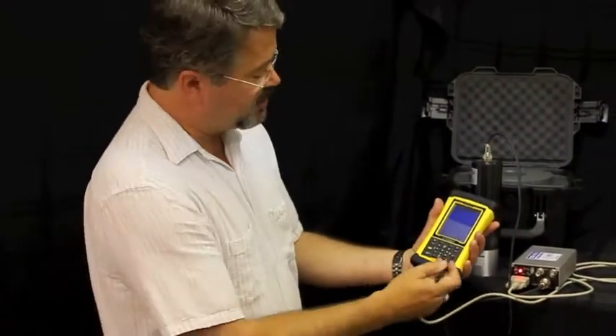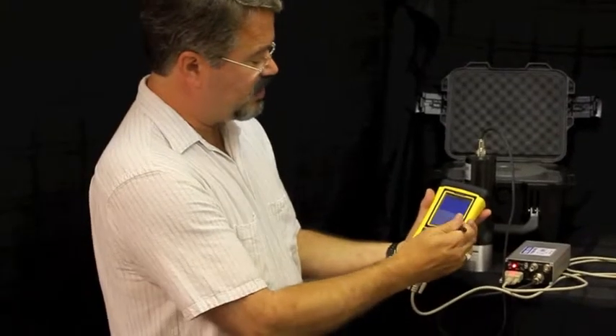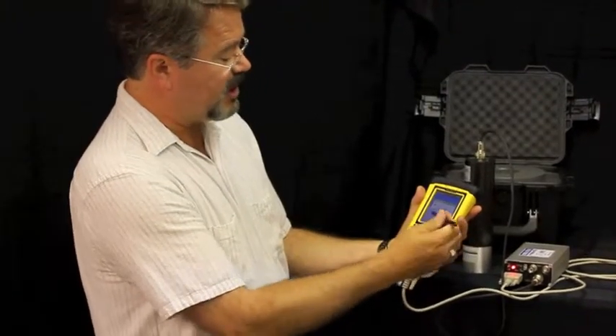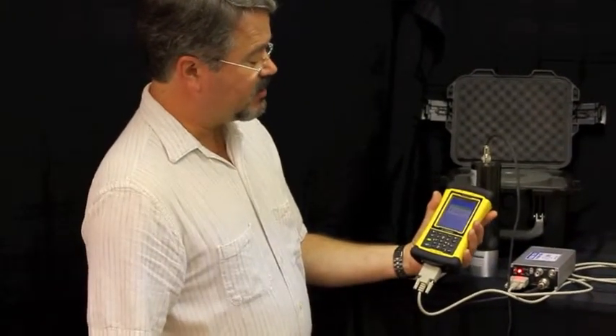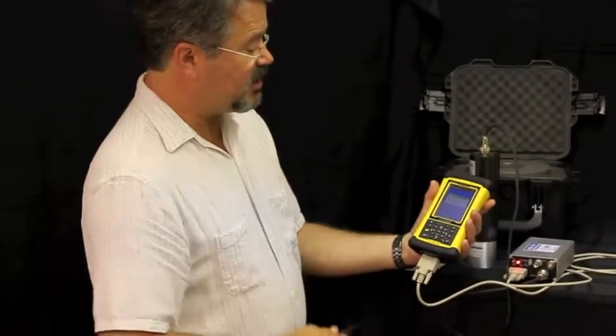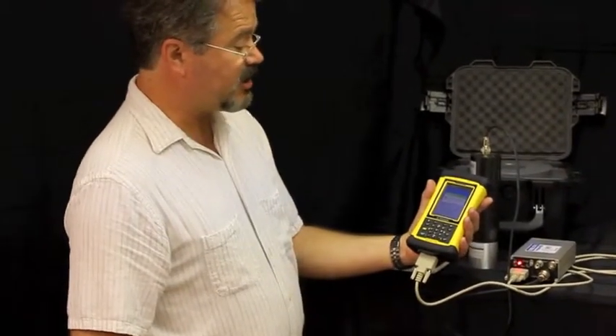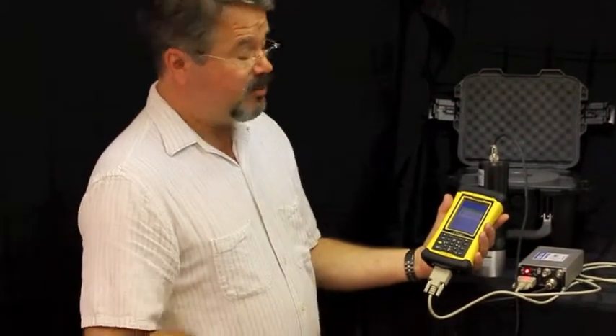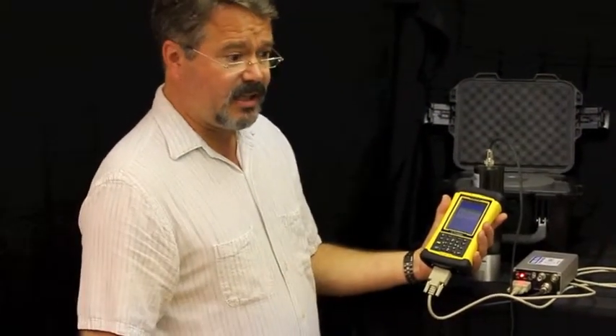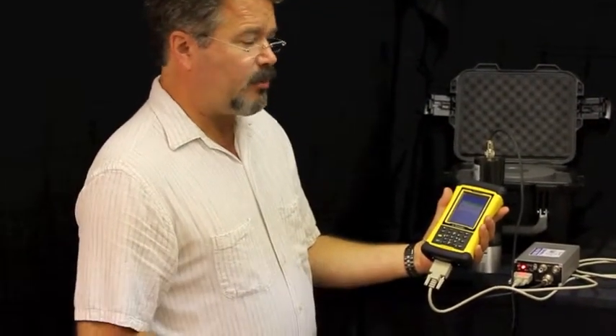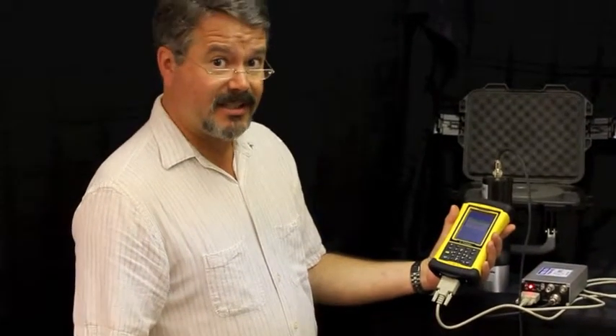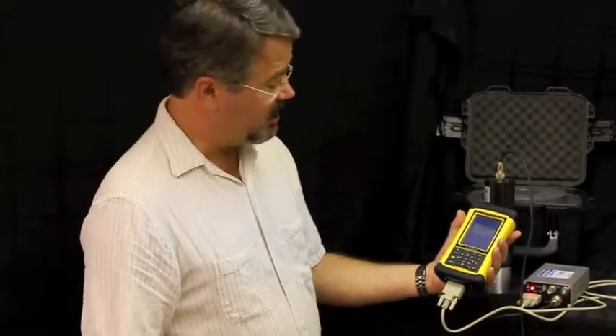still in calibration. So one of the first things that you will be prompted to do, even if you were to attempt to run a sample spectra, is you'll be told that you have to run gain stabilization and source check before you're able to go. And this is a precaution to make sure that the device is operating as it should, as designed.